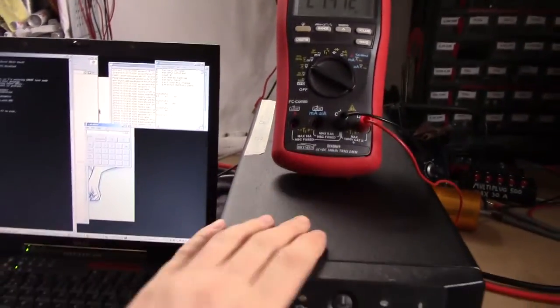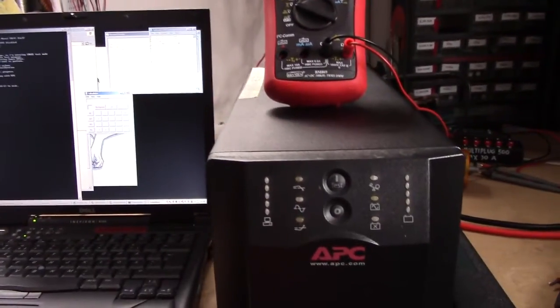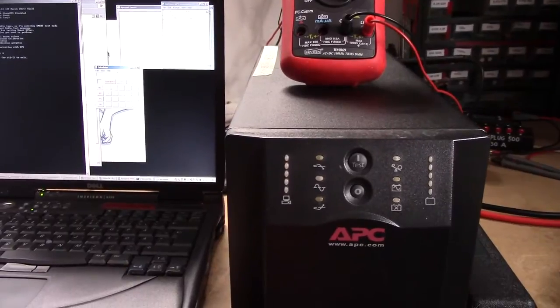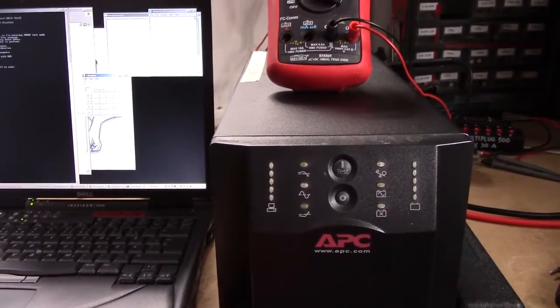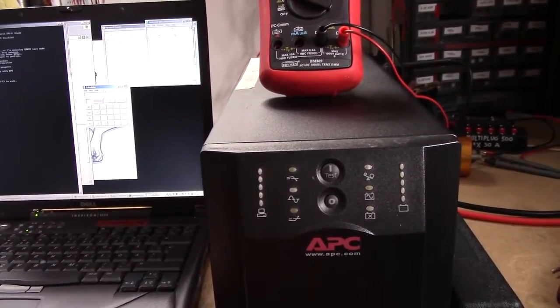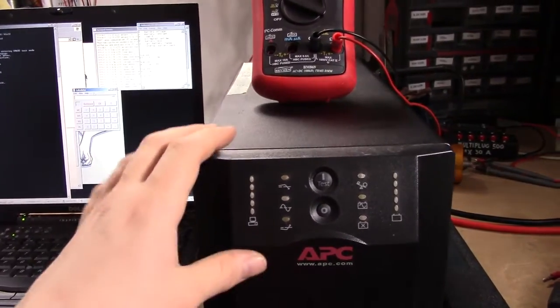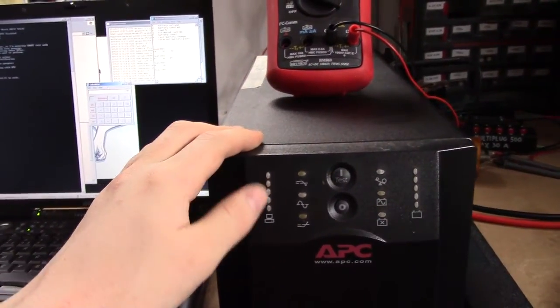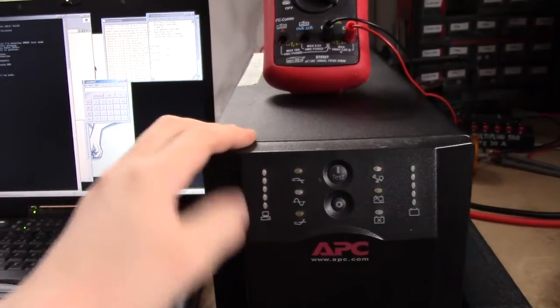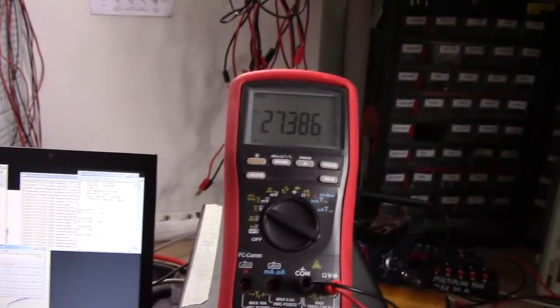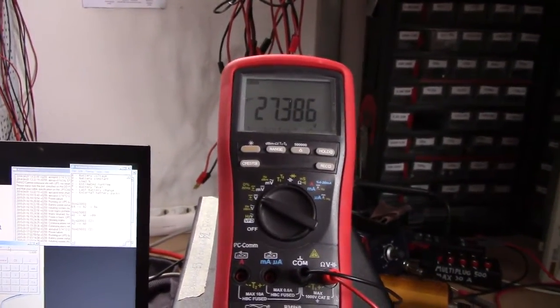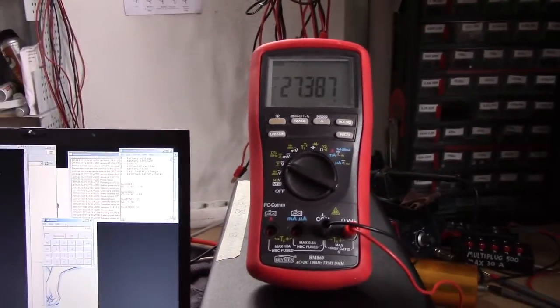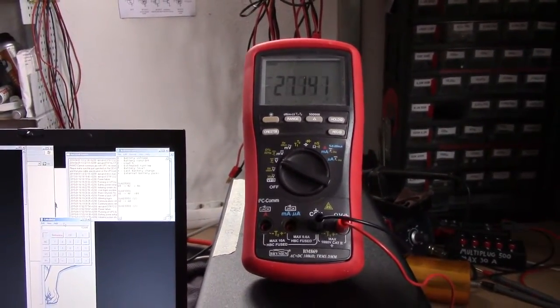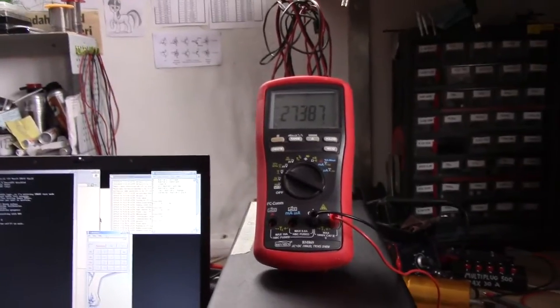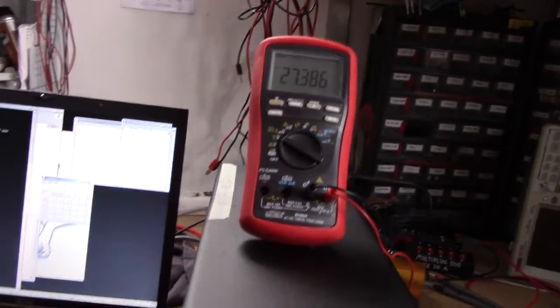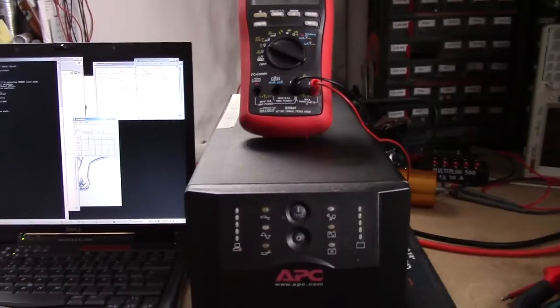These APCs have a bit of a weird habit of changing the battery charge voltage just a little bit, a few millivolts, every time they do the battery presence test, where they just shut off the charger, see if the voltage remains, and then turn it back on. And now we're back at 27.386, so it seems it skips a PWM step or two. Not that it really matters, it's such a small value. I think this will be good.